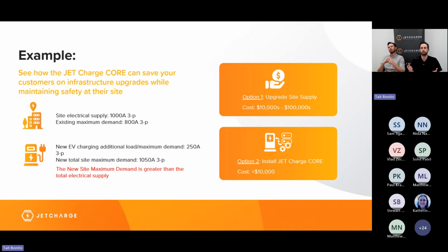So here's a quick example, kind of similar to what I spoke of before, outlining the two scenarios that you can take when running into site constraints in terms of the electrical demand, but we'll take it with some actual figures now. So you can consider a building that has a 1,000 amp 3-phase electrical supply, and you can assume that the building maximum demand for this building has been calculated to be 800 amps 3-phase. So maybe they've done some data logging or some analysis of their interval data from their electricity meter, and found that there's 200 amps spare on this 1,000 amp supply.